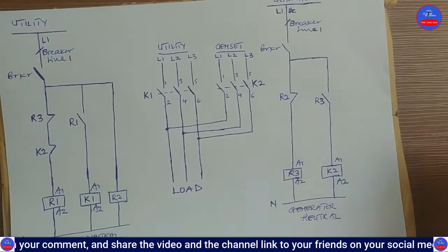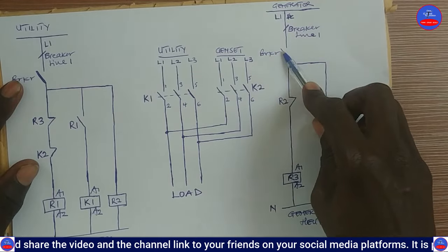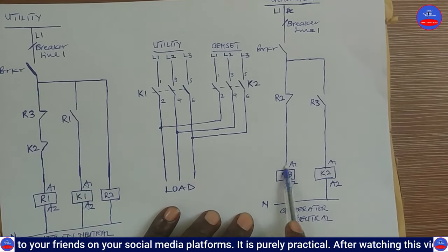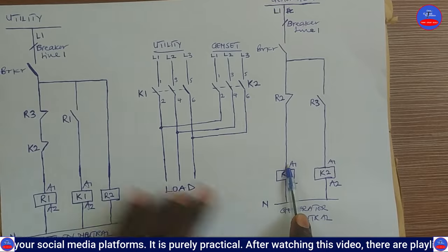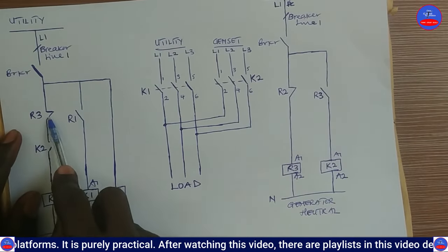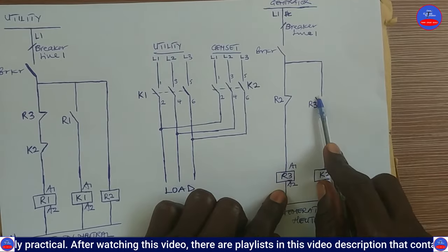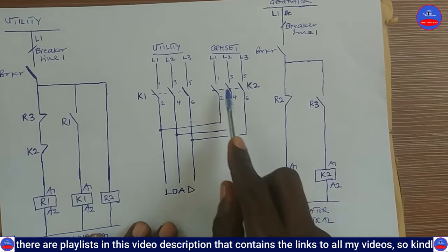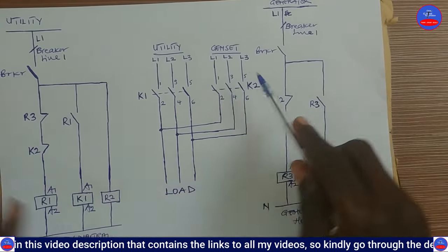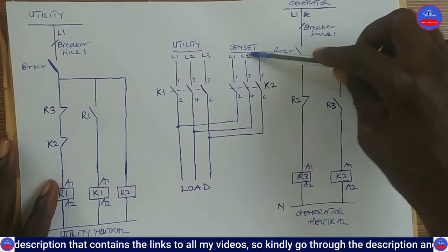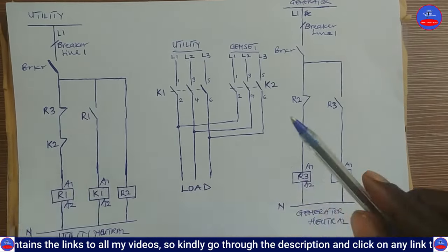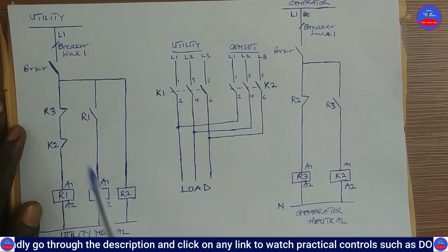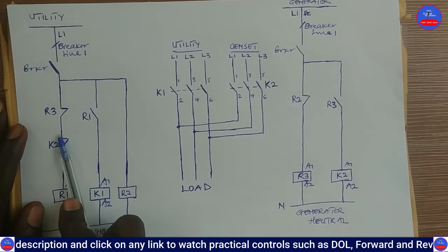Now we come to operate the generator. When the generator is on and its breaker is closed, R3 will energize. When R3 energizes, one contact opens and another closes. When that contact closes, K2 energizes. When K2 energizes, its contacts close to apply the generator power to the load. Now we are operating on the generator. With K2 energized, that contact on the utility side is also open.